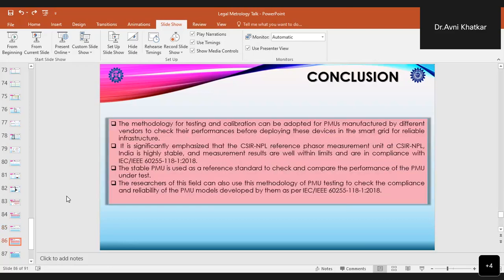So I would like to conclude by saying that the methodology for testing and calibration can be adopted by the PMU manufacturers, by calibrating the PMUs from the different vendors in order to check their performance before deploying these devices in the smart grid for reliable infrastructure. It is also significantly emphasized that the CSIR NPL reference phasor measurement unit is highly stable, and all the measurement results are well within the limits and in compliance with the latest IEEE standard. This stable PMU is used as a reference standard in order to check and compare the performance of the PMUs under test. And researchers in this field can also use this methodology of PMU testing in order to check the compliance and reliability of the PMU models which are developed by them as per the IEEE standard.